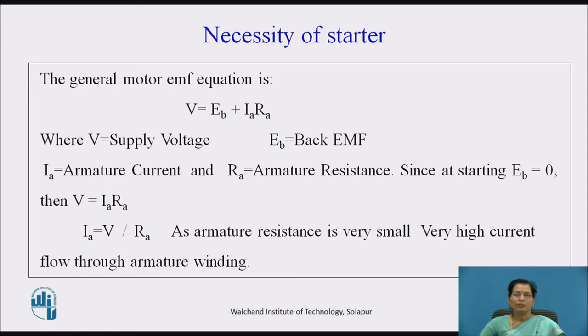In general, the motor EMF equation is given by V = E_B + I_A × R_A, where V is the supply voltage, E_B is the back EMF, I_A is the armature current, and R_A is the armature resistance. Since at starting, back EMF is 0 because the conductors are stationary — back EMF is developed due to cutting of flux by the conductor — if the speed is 0, back EMF is 0, then V = I_A × R_A, so I_A = V / R_A.